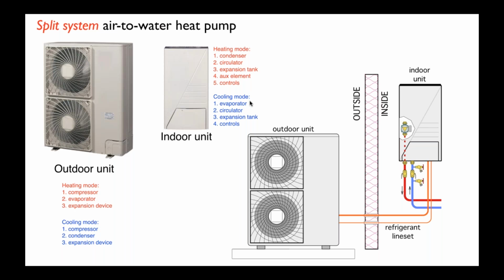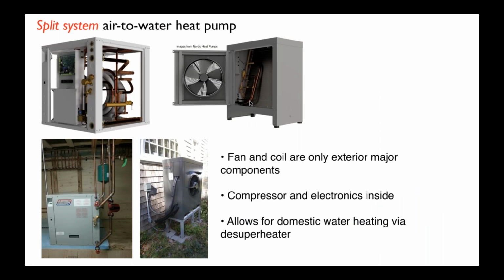So that's the basic difference between a split system and a monoblock, and there are products in both of these categories on the market today. Here's an example one. This is actually a Canadian product, comes out of Maritime Geothermal. This one is a split system. You can see down below, here's the outdoor unit. That outdoor unit in this particular product, Nordic, only has the outdoor coil and the fan. The compressor is actually inside.